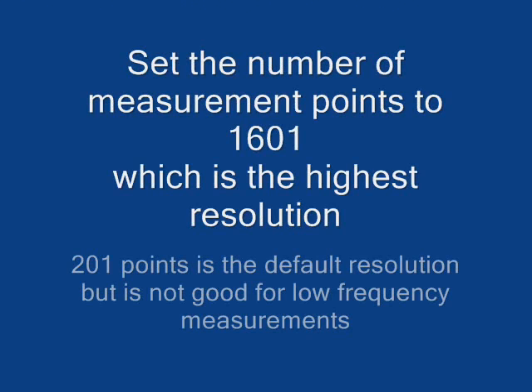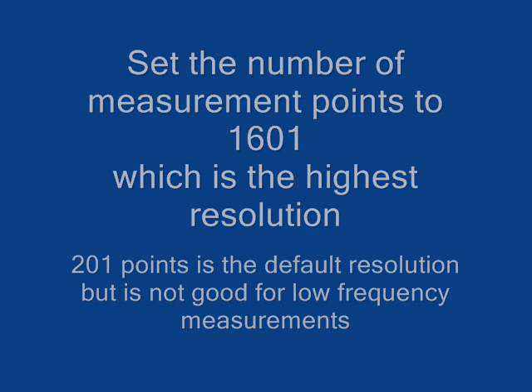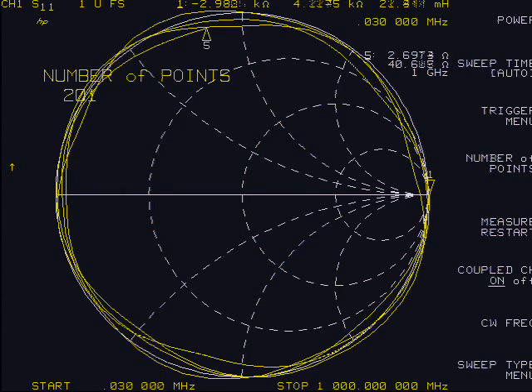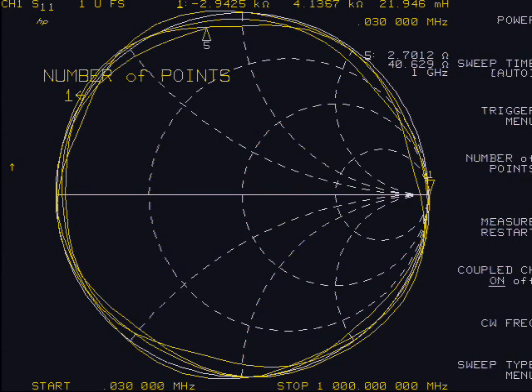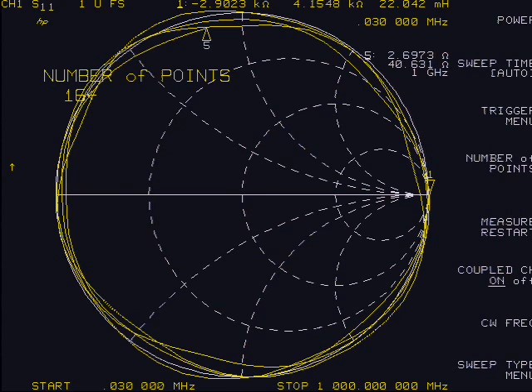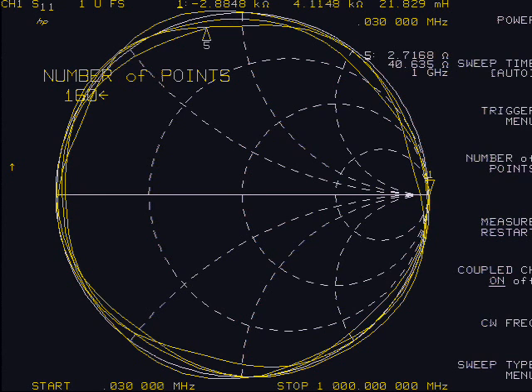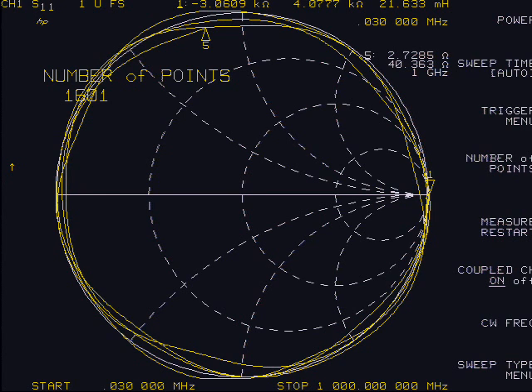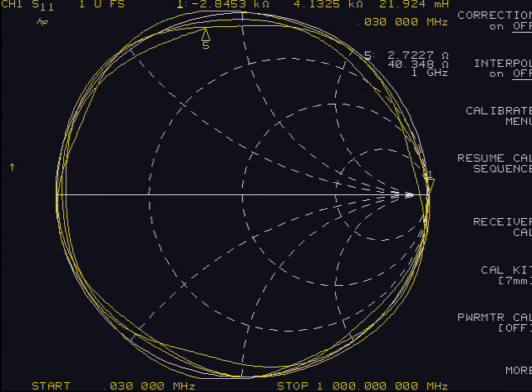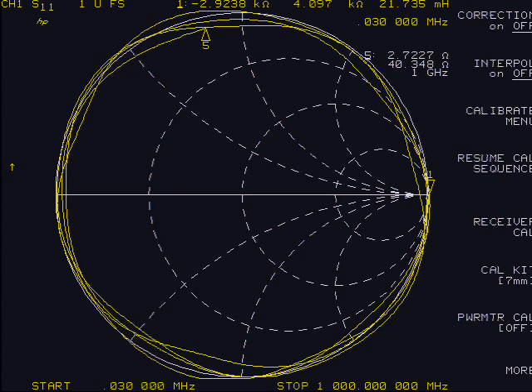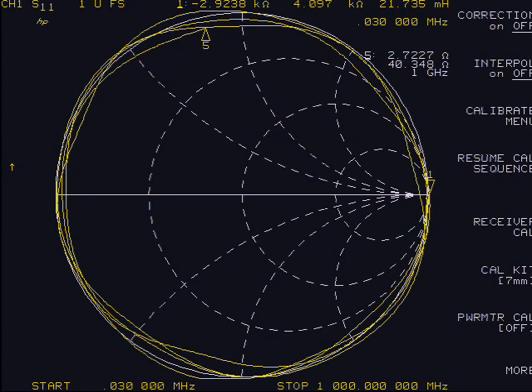Set the number of points by selecting the menu button, then number of points soft key. Use the keypad to enter 1601: 1, 6, 0, 1, then the X1 key. 201 points are the default number of points with 801 and 401 optional, but at less than 201 points, resolution is lost at low frequencies.